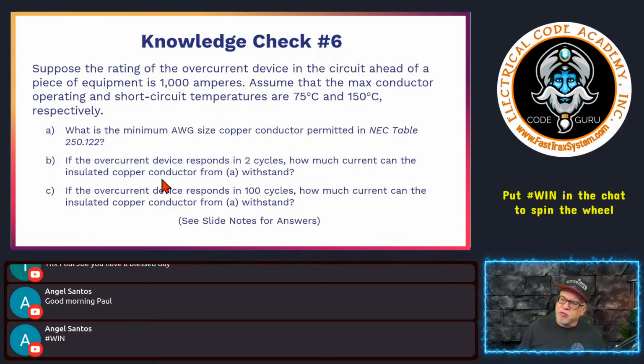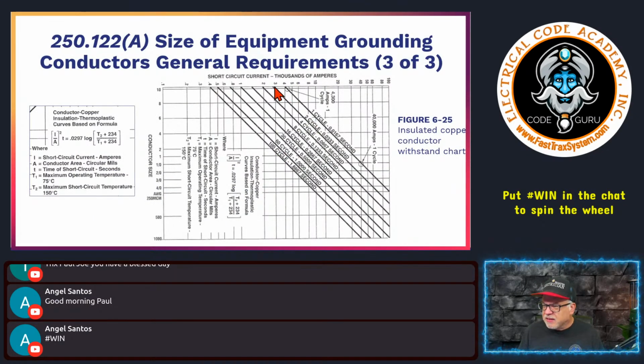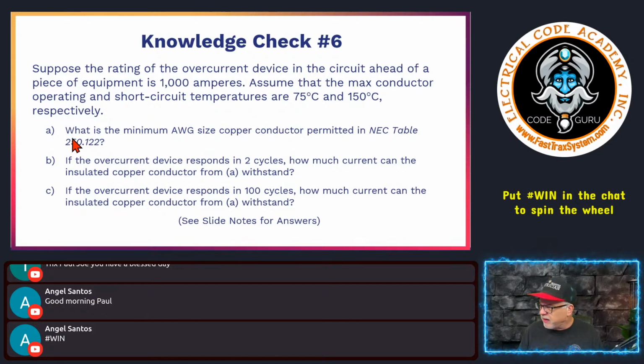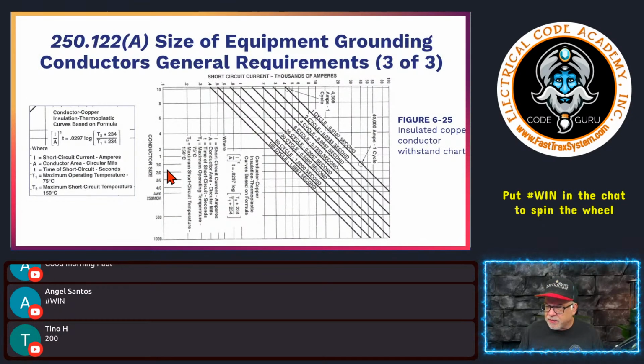It says if the overcurrent device responds in 2 cycles, how much current can the insulated copper conductor from A withstand? Okay, so we got to go back to this type of thing, although I tell you, don't mess with this. I tell you don't do this, but I'll go back. So 2 cycles is right here. We said this was a 2-aught, so we're going to go down to a 2-aught right here, follow this over, right here. This is the 2 cycle, and it looks like it's right about in the middle. So we'll say about 35,000 at 2 cycles. It can handle about 35,000 at 2 cycles.